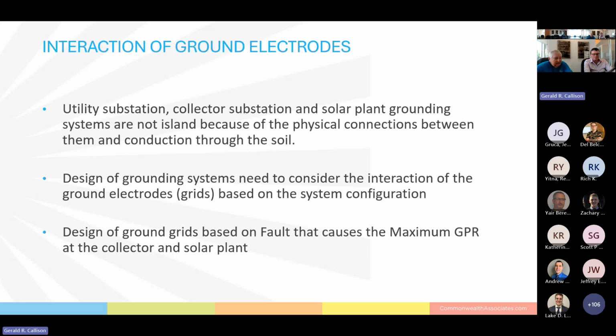Okay, so what is the interaction between the electrodes? Well, if you have a utility substation, a collector substation, and a solar plant grounding system, and I'm going to use solar plants as the typical example, and the same thing holds true for wind generation, they're not islands. They're not separated completely from each other, because they have the physical conductions that I talked about, and also the conduction through the soil. The design of the grounding system needs to consider this interaction in order to make sure that you're designing it to the correct fault current that is available at the different sites. And you need to design the ground grid based on the fault that creates the highest or the maximum ground potential rise at the solar and the collector plants.